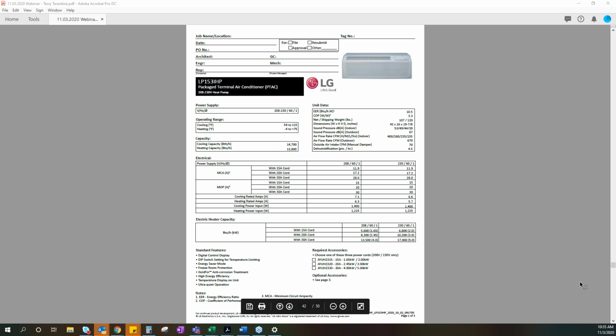All right, PTAC. This is literally hot off the press. This was sent to me yesterday. We are seeing two manufacturers. This one shows LG, Friedrich is the other one, where they are coming out with inverter-driven PTAC units. Inverters are modulating compressors, so they're trying to integrate some VRF technology into some lower efficiency typical systems.